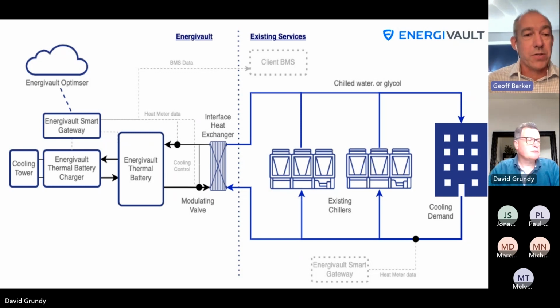The EnergiVault effectively comprises three main elements, if you ignore the cooling towers as a fundamental part of the refrigeration: a thermal battery, which is a volume containing the ice slurry, the latent energy; a thermal battery charger, which is the primary refrigeration plant—in the current case an ammonia system; and an EnergiVault smart gateway, which provides the interface for control, both to external cloud-based optimizers, which are our developments in the EnergiVault platform, and also connecting to the client's BMS, which is still dominant in terms of how things are controlled. So essentially you've got a store, a charger, and a smart intelligent control element connected via a heat exchanger to the system.